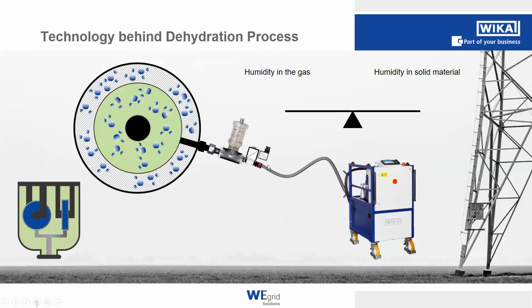So what does happen in detail when we connect our GAD? Like I said, we have the measurement box in front of the hose, which we connect to the gas compartment, which we can see here. We can see the metal walls of the compartment, and we have the gas compartment room where the SF6 gas is inside. And we can also notice that we have humidity in the compartment walls as well.